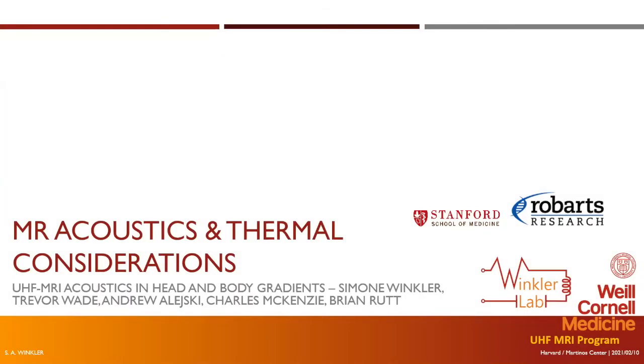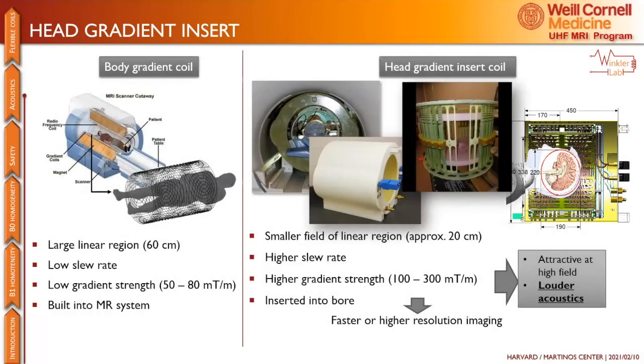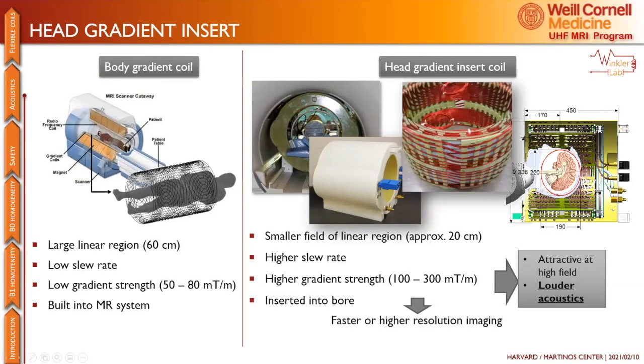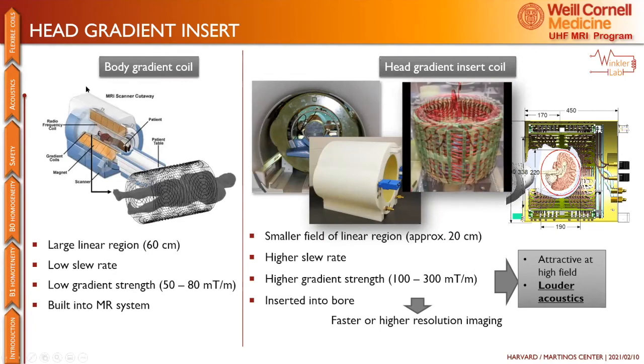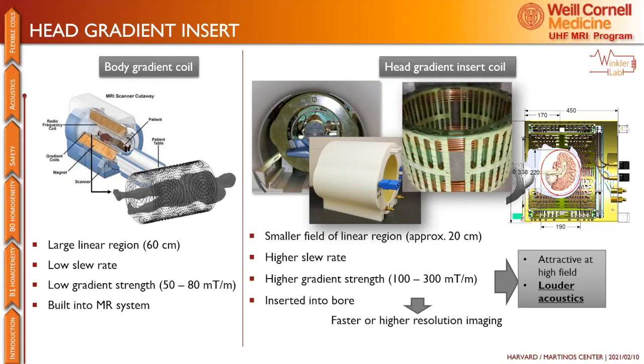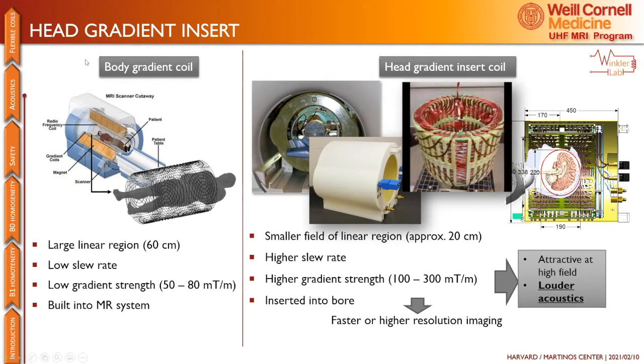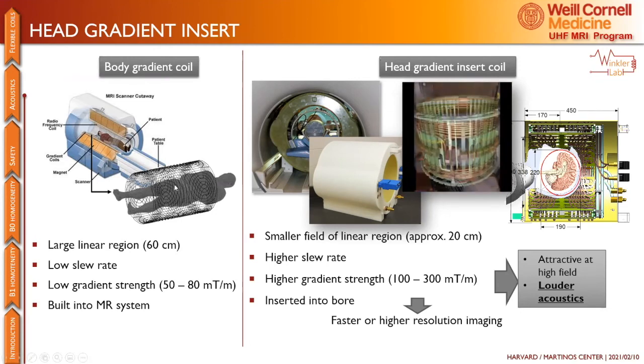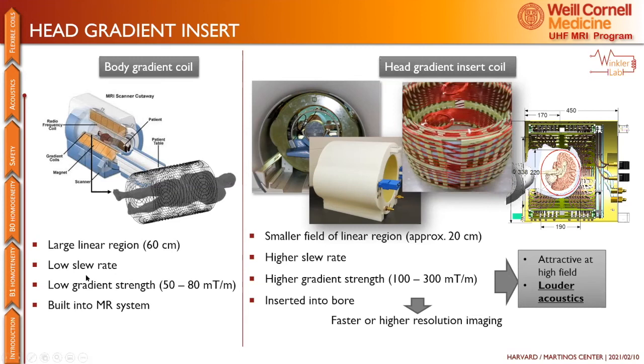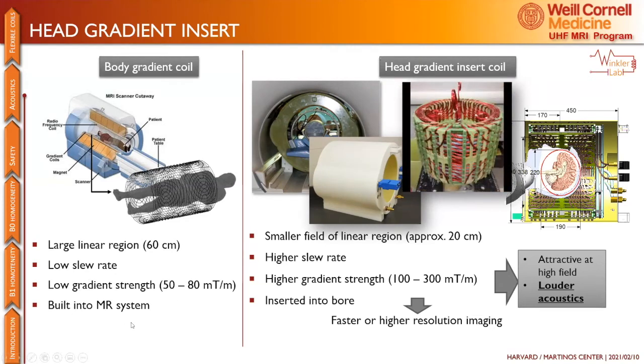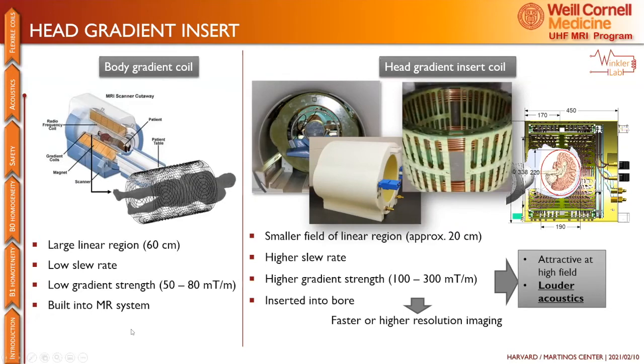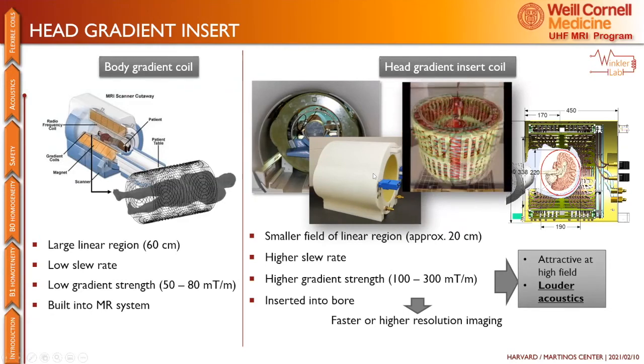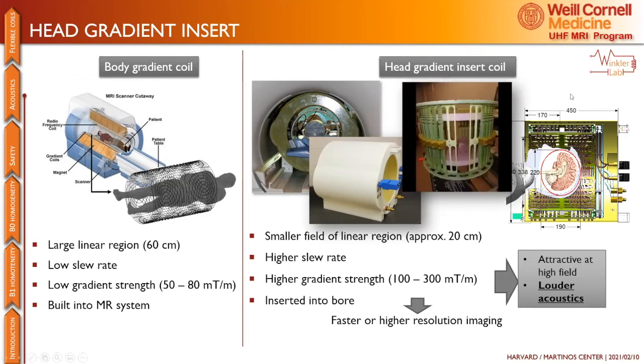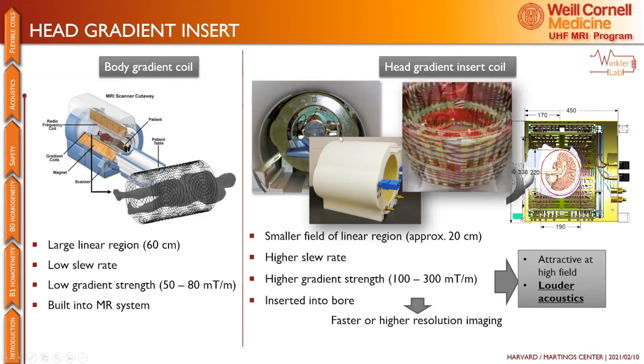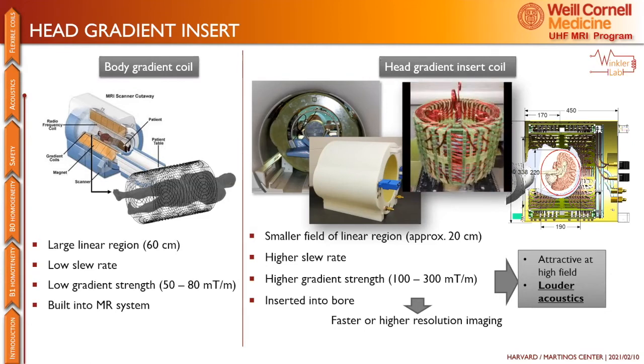We worked on this mostly with Robarts in Canada, and I want to mention a few things about gradients. Really the majority of scanners have a built-in body gradient coil. It covers most of the body dimensions and has a large linear region, but it's not very strong and has a low slew rate. So it's versatile, but not very strong. Some people have been working on head gradient specific designs. It's the same thing, but it goes into the bore as you see here, and you just put your head in there, and it doesn't really work on other anatomies as much.